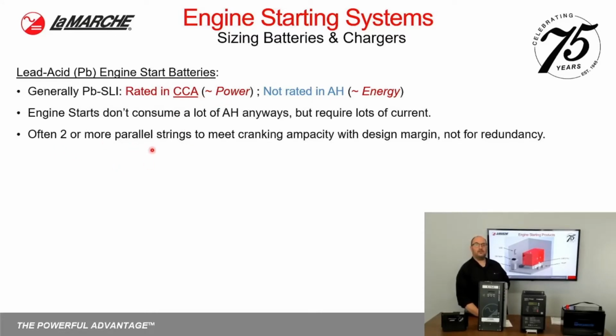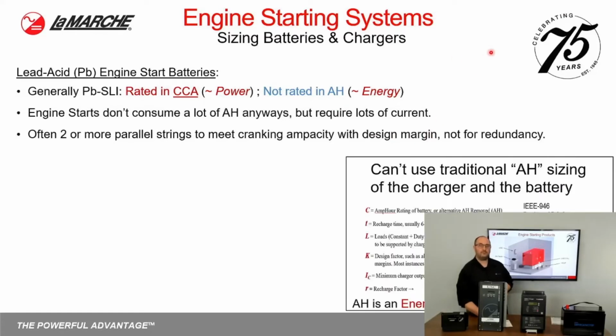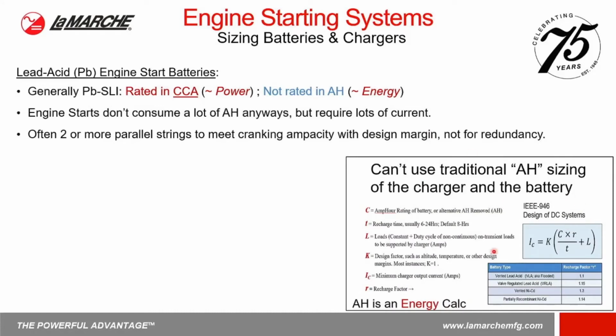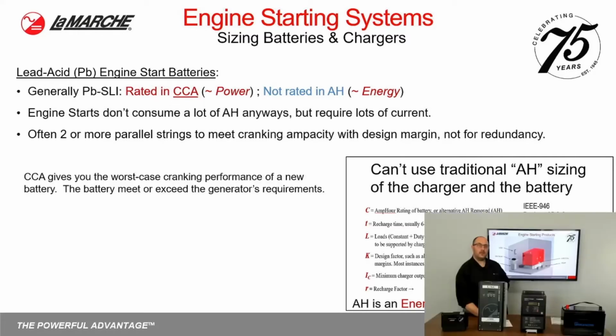So quite often, 2 parallel strings are used to meet the cranking ampacity, and they're not really sized in for redundancy. They're really designed in for design margin. The typical battery sizing that we would use in other stationary markets, such as utilities, substations, oil and gas applications, are energy applications, so those are sized in amp hours, and you would normally go through this formula. This is how LaMarche sizes, according to IEEE 946. But because you don't have an amp hour rating, you really can't use this system.